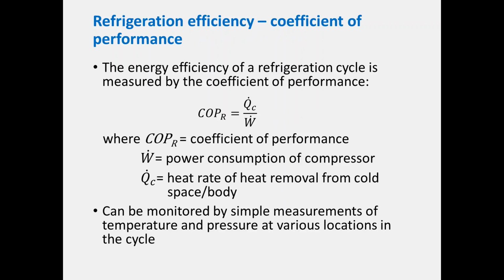So very finally, we want to look at the refrigeration efficiency, best measured by the coefficient of performance, where that coefficient is the ratio of the heat being removed from your space or the product, the body, compared to the power consumption. I've got the compressor there, but it's really not just the compressor, it's all those auxiliaries.